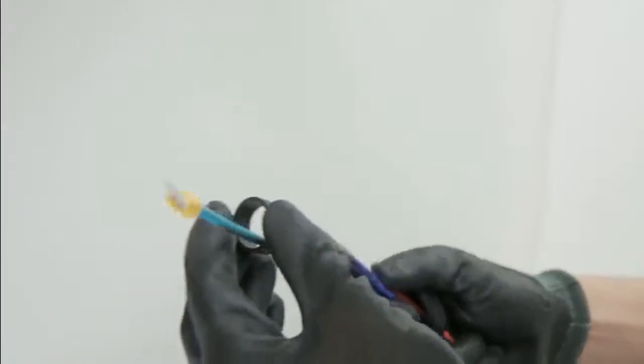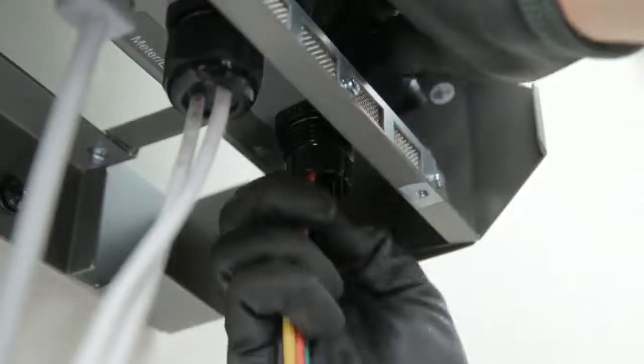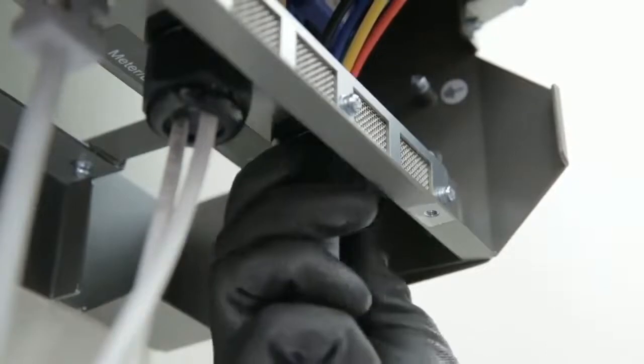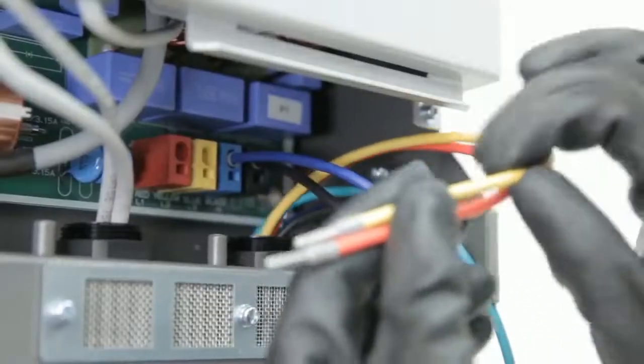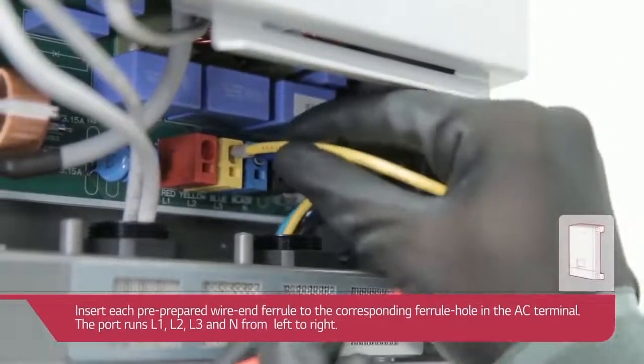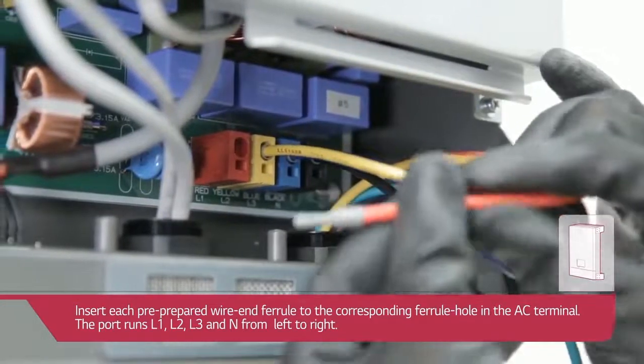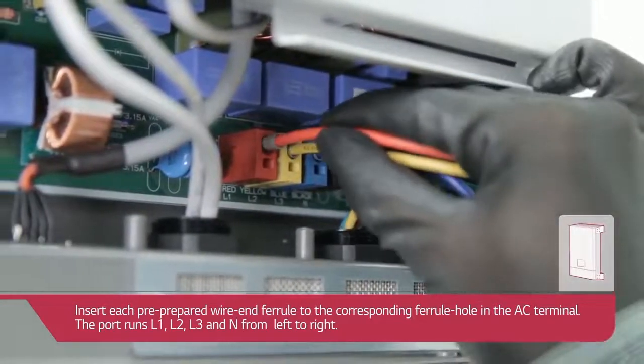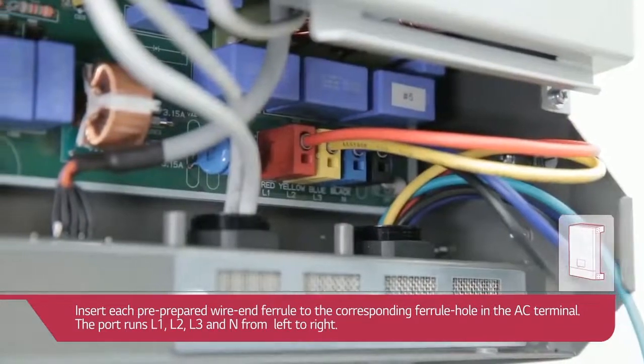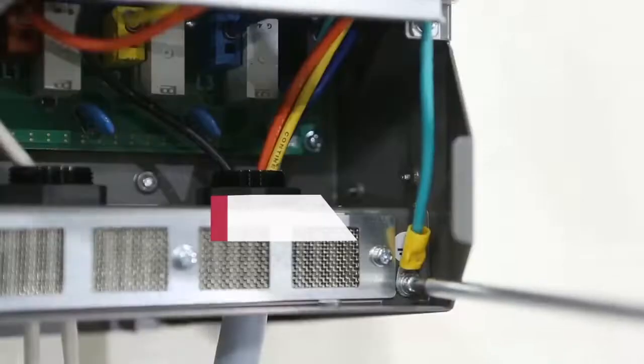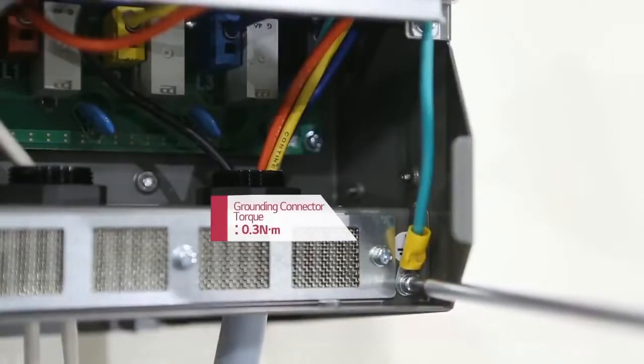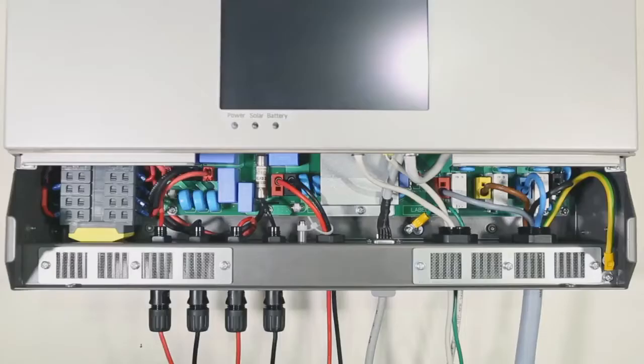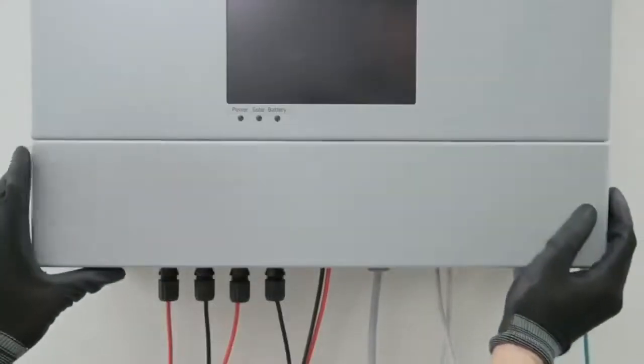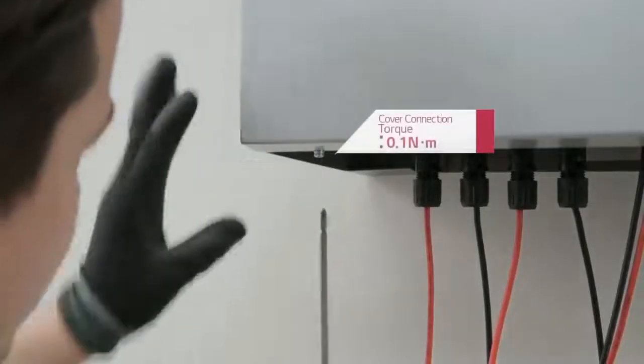Release the cap of AC cable conduit. Insert the AC cable on the power grid through the cable conduit. Insert each pre-prepared wire end ferrule to the corresponding ferrule hole in the AC terminal. Connect the grounding wire to the grounding connector. Now, all the cables are connected to the PCS. Assemble the lower cover to the PCS.